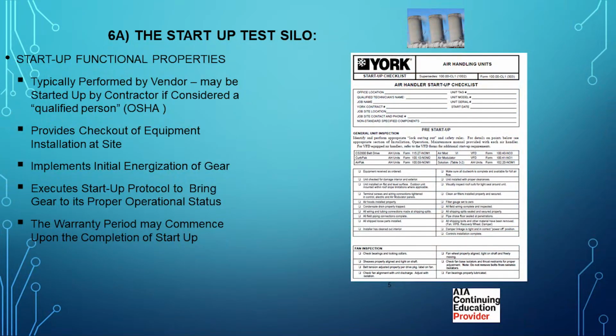The startup silo works the same way. It is a typical startup form. It's performed by the vendor, may or may not be witnessed by the commissioning agent. It's very focused on the equipment, not necessarily the system. So if your air handler is the air handler with an outside exhaust fan and VAVs and whatever, they're looking at that component. You might actually have the tab guy have to come in, the BMS guy have to come in, the VFD guy have to come in. They may not necessarily be looking at the equipment at the same time and adjusting it at the same time with everybody.